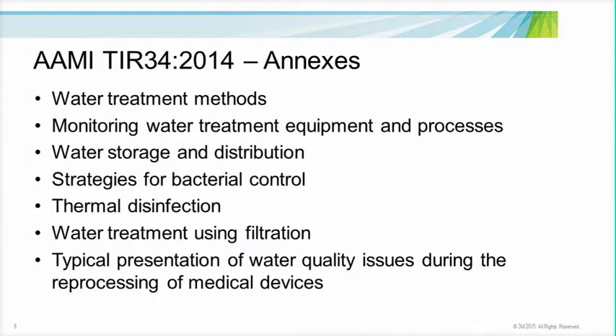TIR 34 also has many very important annexes, which include the Water Treatment Methods Annex, which goes into every process that may be incorporated into the water quality process. We will be covering this in detail later. It also includes what substance is removed by each process and examples of these specific water treatment processes. The Annex on water treatment equipment and processes shows how to define the preventative maintenance on the entire water system. This includes how often filters should be replaced, etc.